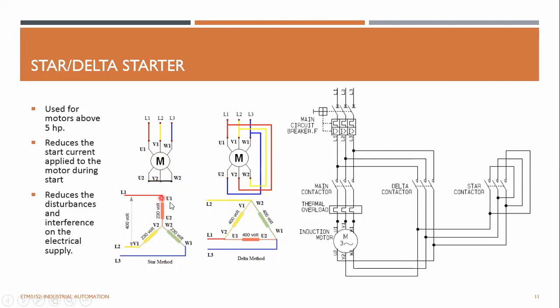And to achieve this wiring, you can't change the wiring manually, right? You can't go and open the motor terminals and wire this, that would be a pretty silly thing. So you definitely need these kinds of contactors to perform this task. You also need this kind of 6-terminal wiring box on the motor in order to achieve this. If the motor has only 3 terminals, you can't do this operation, because motors less than 5 horsepower typically come with 3 terminals. You just plug and play. But in high horsepower motors, the terminal block always has 6 connections, so the user can use it for this kind of application.